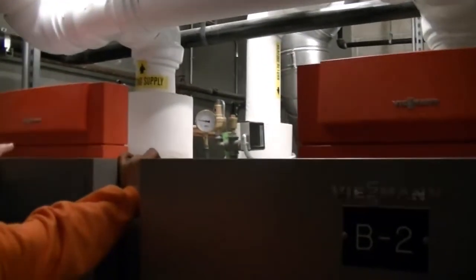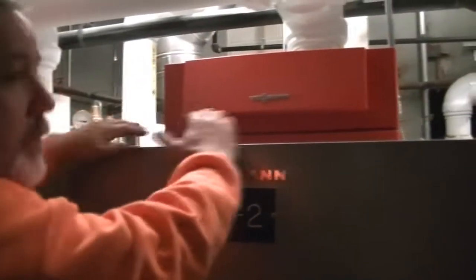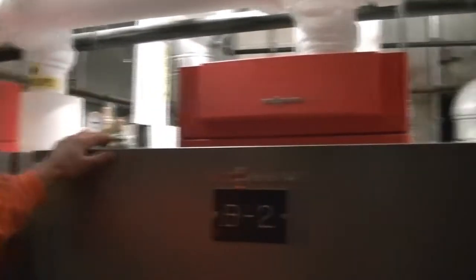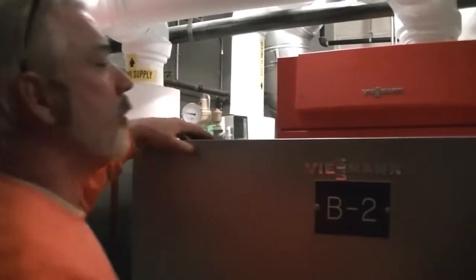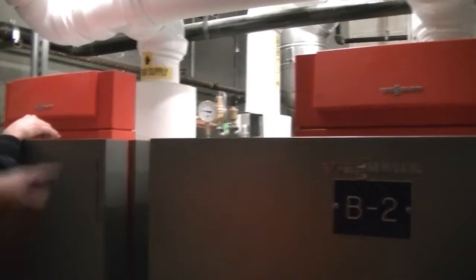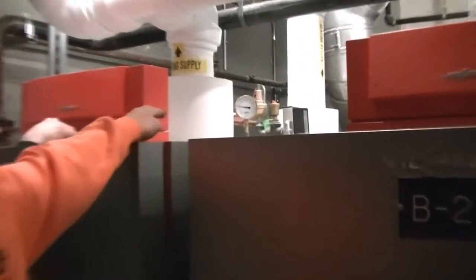If you walk up to the boiler and there's no power to the boiler, okay, no power to the burner, right here, this display is off, but you see power on the boiler control panel, and an alarm, generally means you trip the low water cutoff. If you do trip that low water cutoff, you can reset it. If it doesn't reset, that means there's an air pocket in there. Two ways to get that out of there.